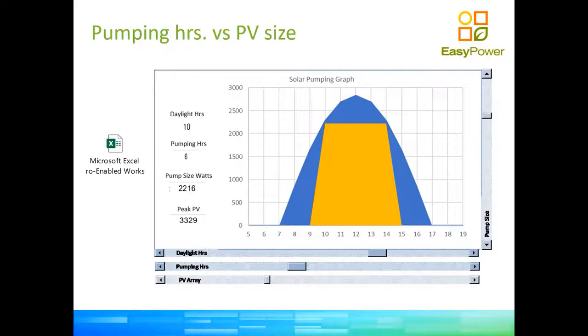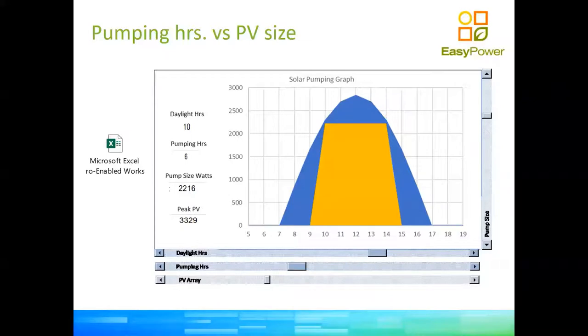Assuming no cloud conditions, the blue power shape is quite nice. As the day progresses, eventually there is not enough power to run the pump at maximum, so the inverter starts backing down the frequency — slowing the rotation — until there is not enough power to keep frequency and voltage stable and the inverter switches off. If you had an AC supply connected to this inverter, there would be an automatic changeover to AC if you want to pump 24 hours a day.